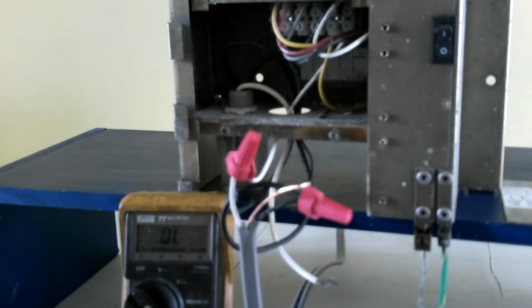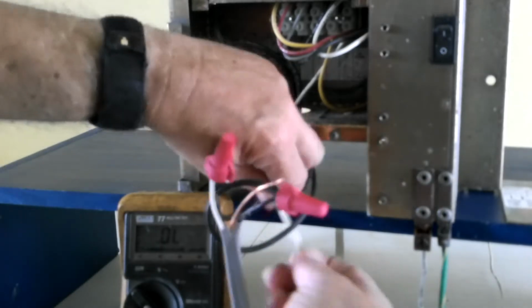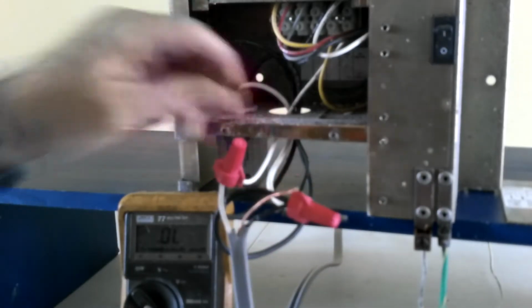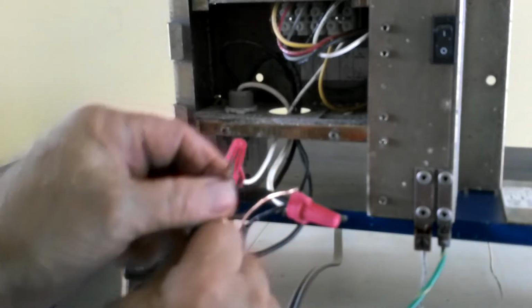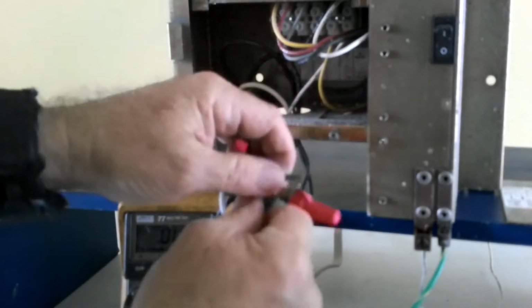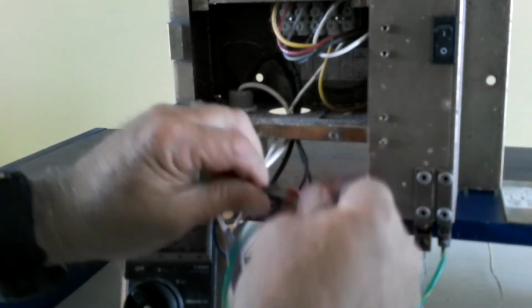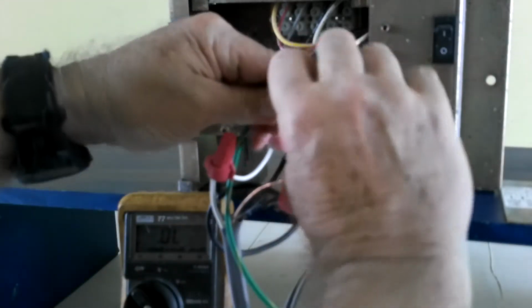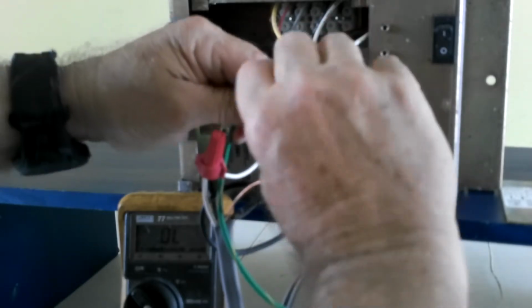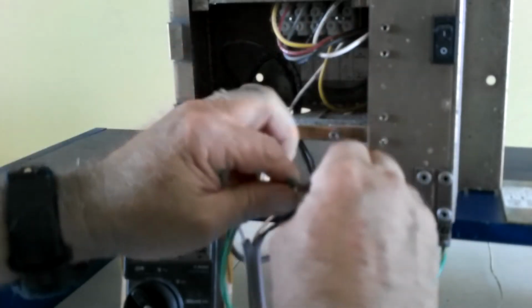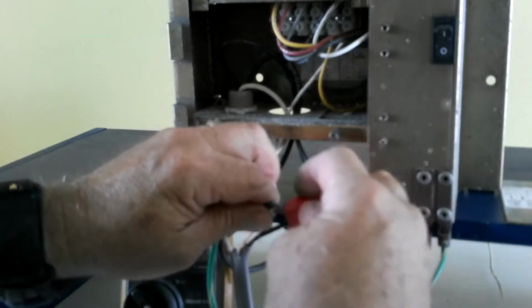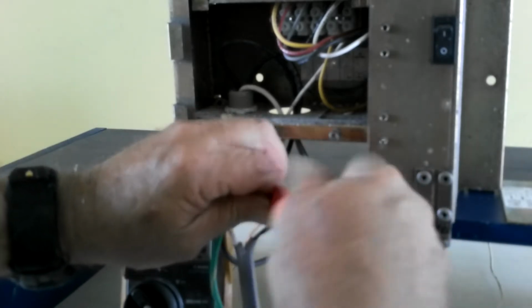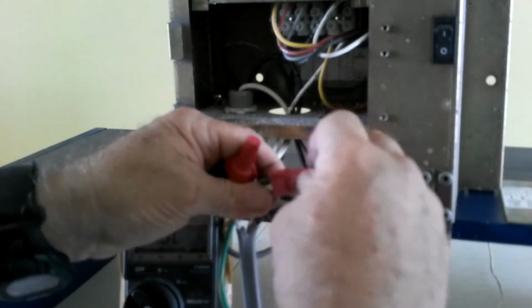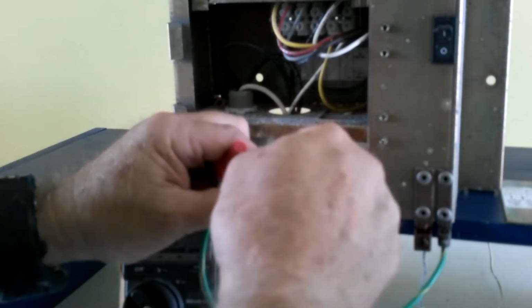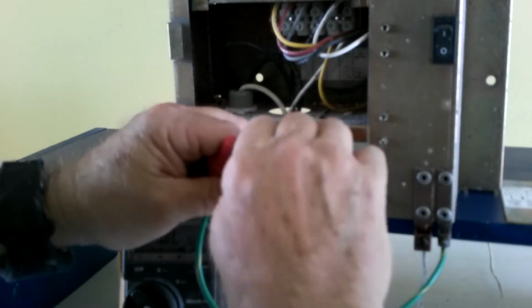And the final step is to connect the white wire from the surge arrestor to the earth-ground connection going to the ground rod by the unit, and those need to connect together, and then connect to the bare copper ground in your power supply wire. If this connection is not made, the surge arrestor cannot function properly, and even though it's there, if it does not have good solid ground connections to earth ground, it won't function to protect your equipment.